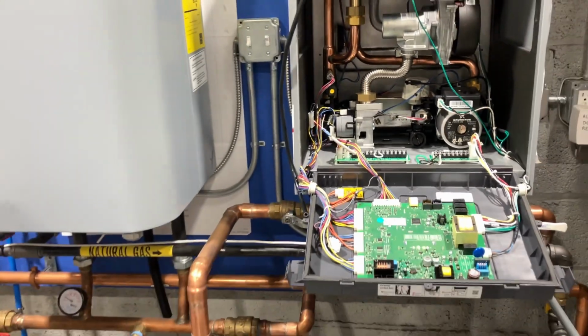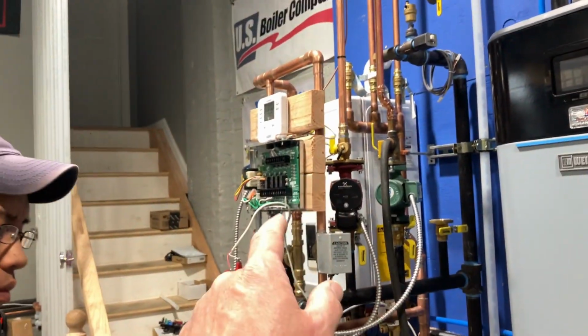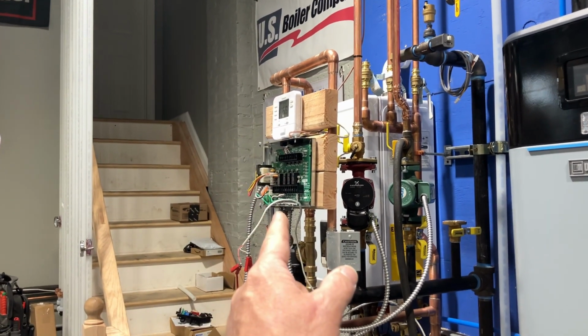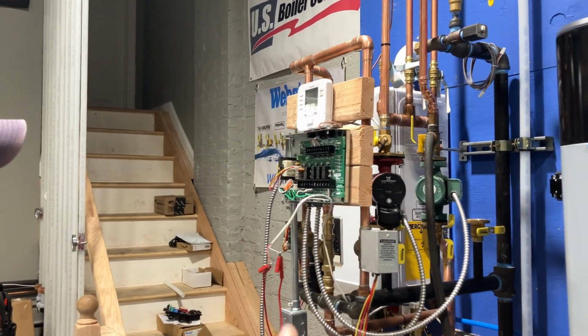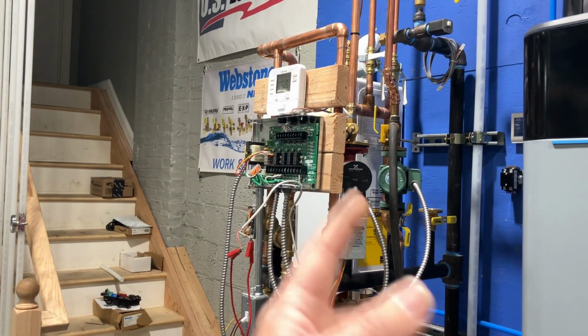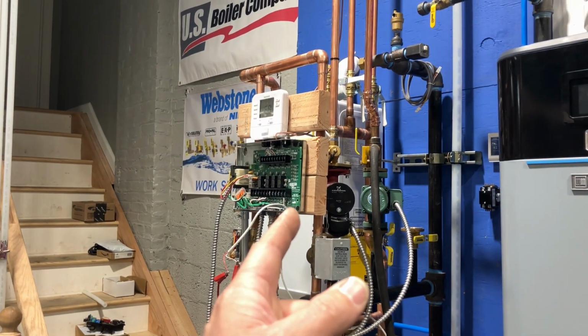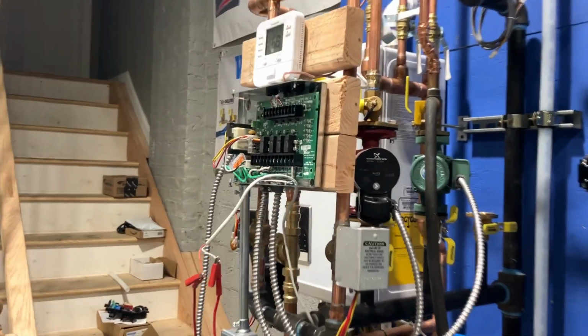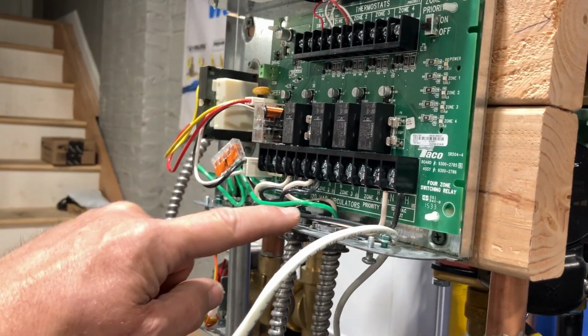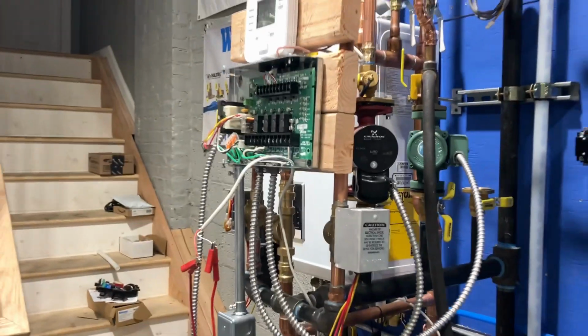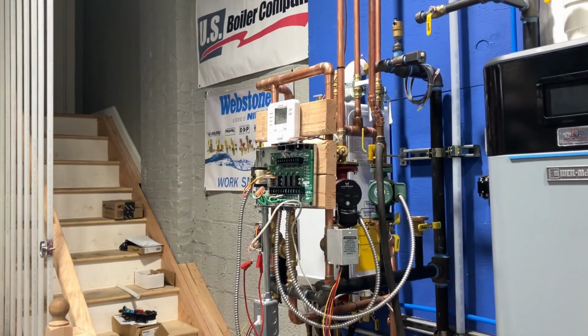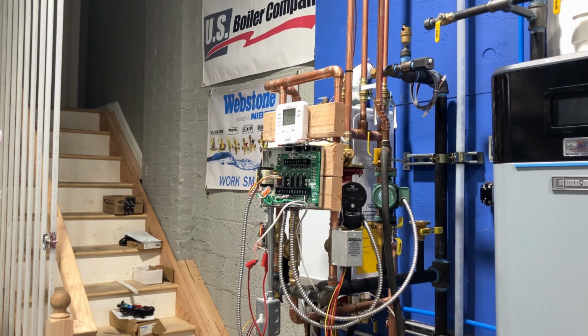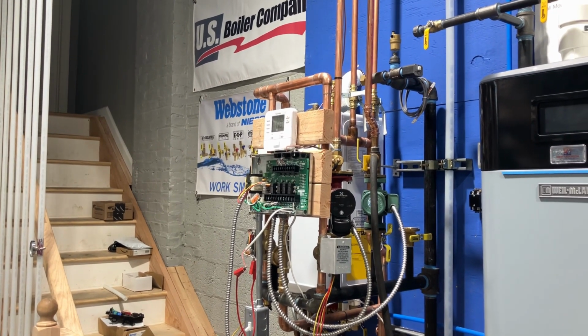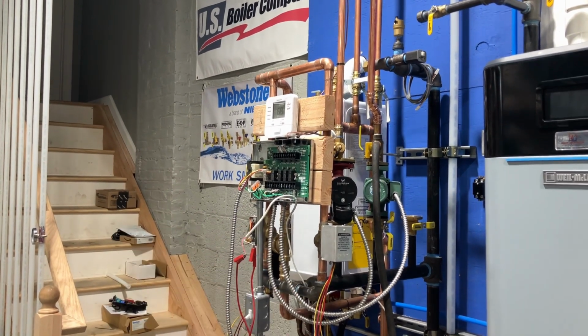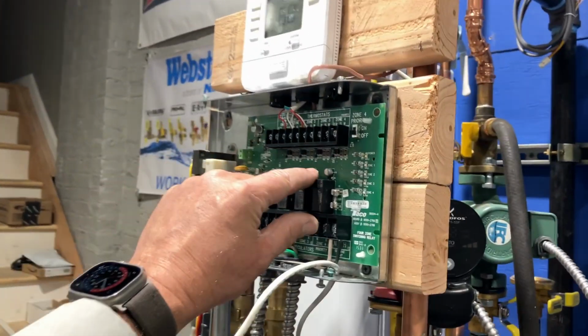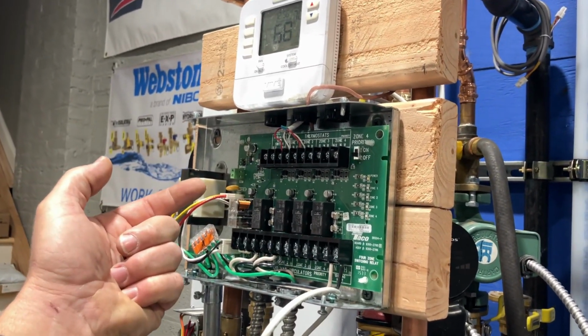Now, based on what we saw, it is likely that the SR504 switching relay had a problem, an electrical something went wrong with it. It's a brand new install. We're going to check for any visible shorts on any of the low voltage, any of the line voltage control wiring. If none are present, we're going to swap out the control with a new one, and hopefully the problem is solved and it was just a manufacturing defect. Maybe something went wrong, but let's pull this circuit board, take a look on the opposite side, see if we see any damage, what have you.